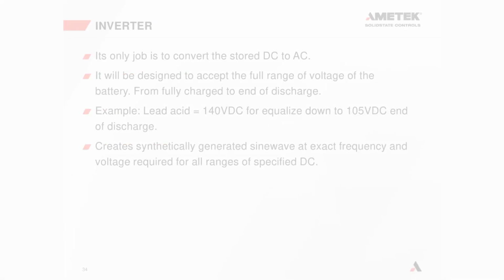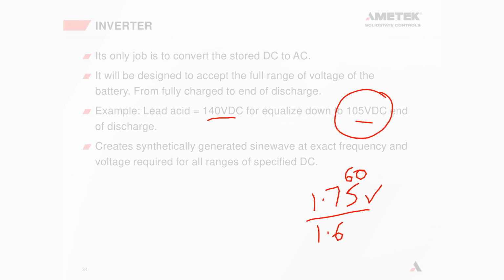And then the inverter just takes that DC, and it has to be designed to accept the full range of voltages from that battery. And as I mentioned, for a lead acid, it's going to be 140 volts for equalize down to 105 volts, which is the end of discharge for the battery. Once again, the manufacturer may say, okay, at 1.75 volts, we say that is the end of the discharge. There's a little bit of a safety margin there. You can usually go down to 1.6 if you really wanted to, but you want to stay away from that if at all possible. So they'll say 1.75, and if you multiply that by 60, you get 105 volts.